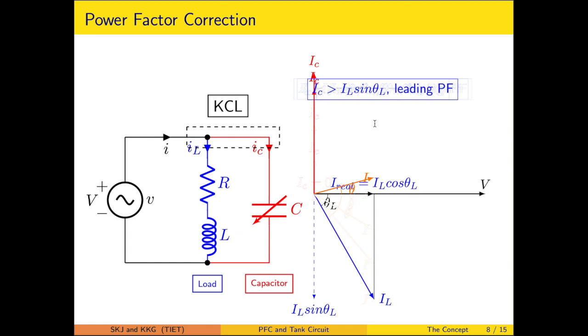So this particular power factor correction we studied for different cases. The power factor correction is achieved by varying the compensation level, and that compensator is placed parallel to the industrial load. The one point to be highlighted is that the load is taken here as inductive, so the compensator is of capacitive nature. If the load somehow comes out to be of capacitive nature, then the compensator has to be of inductive nature like this.